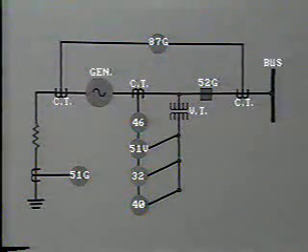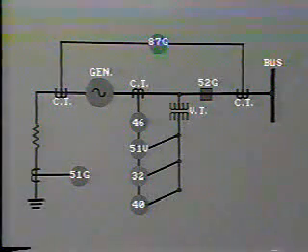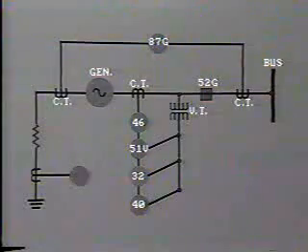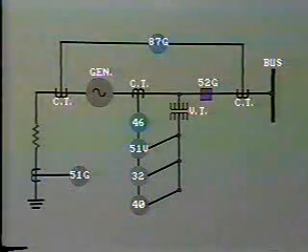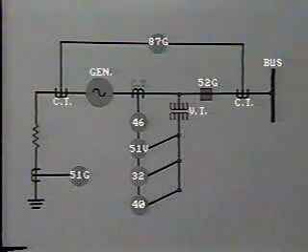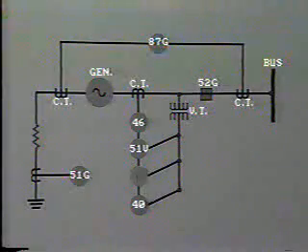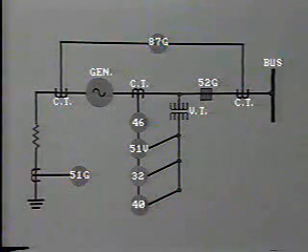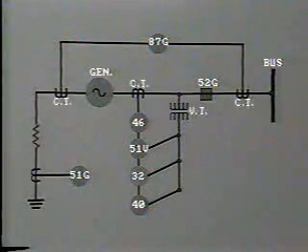A generator connected directly to a bus through circuit breaker 52G. You can already recognize some of these device numbers. 51G is a time over current relay in the neutral to ground. 87G, a differential relay across the generator. What is this 46? A negative phase sequence relay. 51V is a voltage-restrained time over current relay fed by the CT in the generator output, and a voltage transformer, which also feeds a directional power relay, 32, and a loss of field relay, 40.